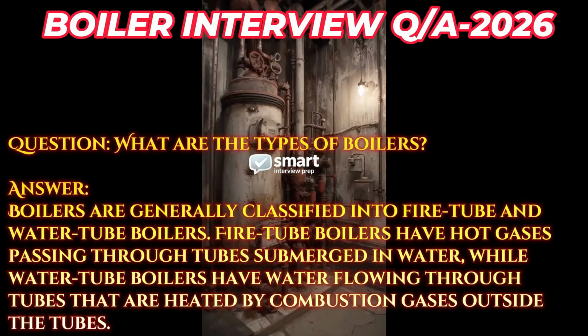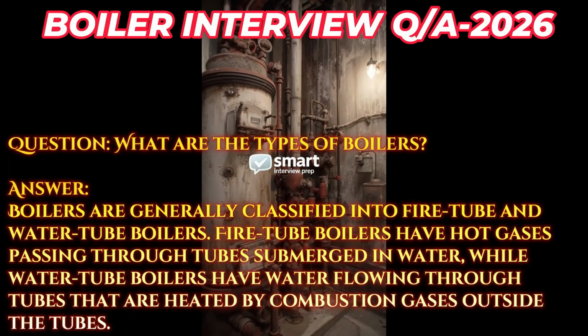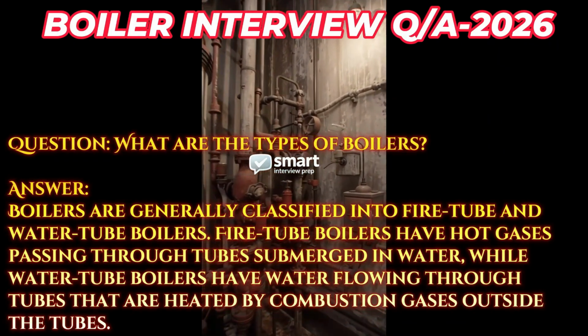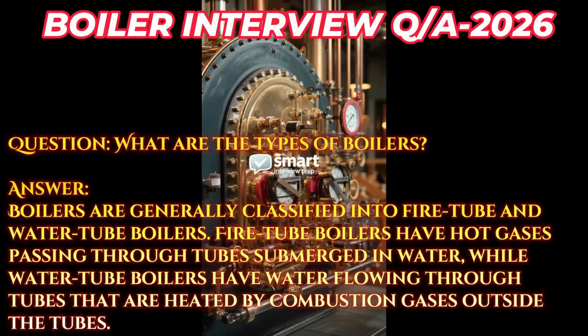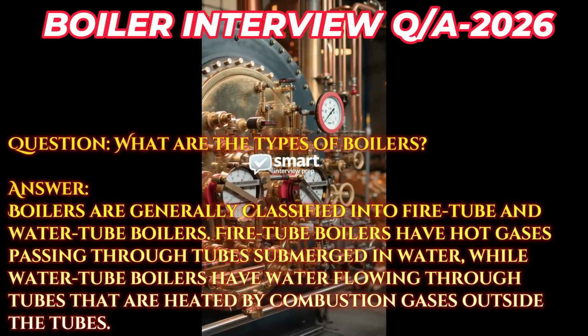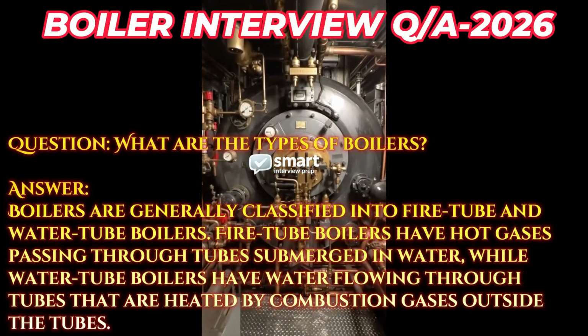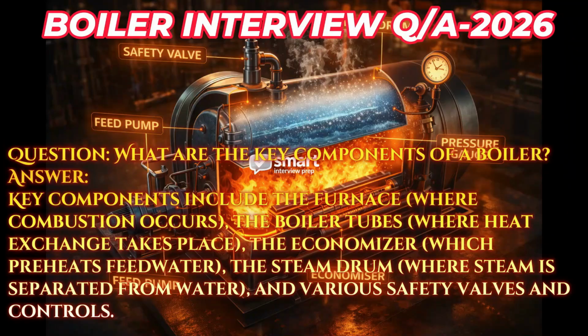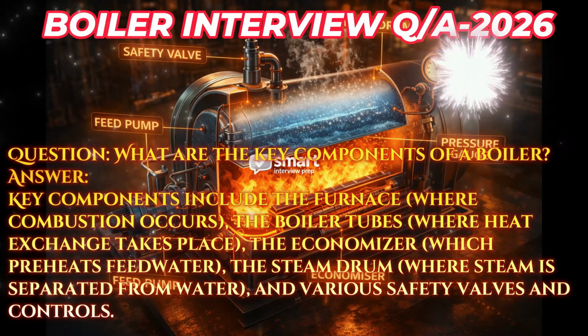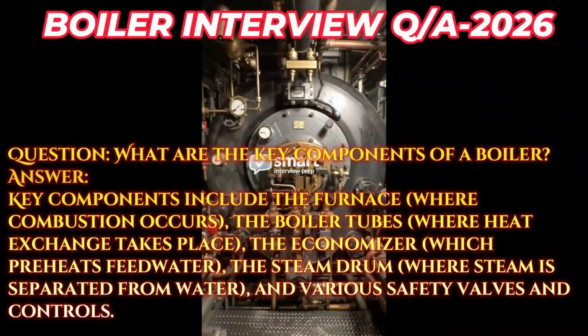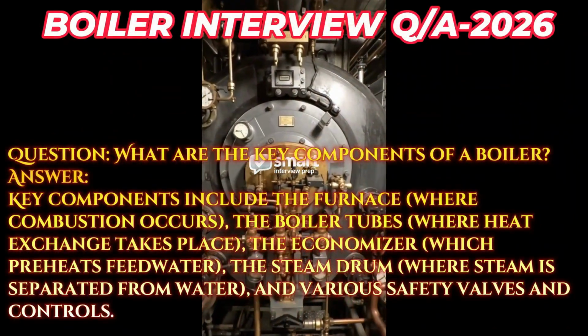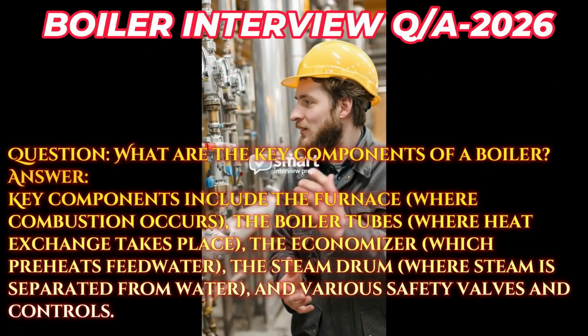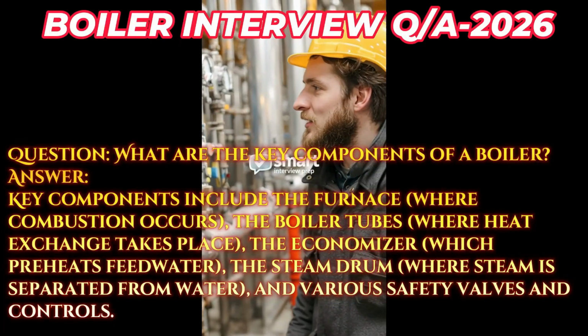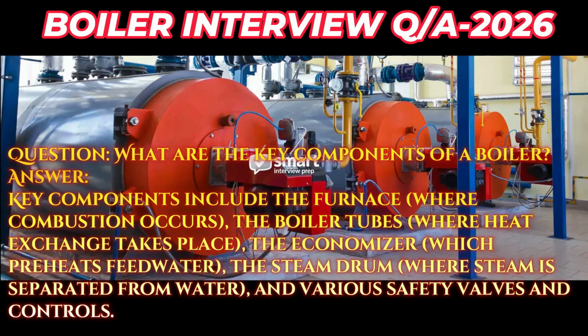Boilers are generally classified into fire tube and water tube boilers. Fire tube boilers have hot gases passing through tubes submerged in water, while water tube boilers have water flowing through tubes that are heated by combustion gases outside the tubes. Question: what are the key components of a boiler? Answer: key components include the furnace, where combustion occurs, the boiler tubes, where heat exchange takes place, the economizer, which preheats feedwater, the steam drum, where steam is separated from water, and various safety valves and controls.